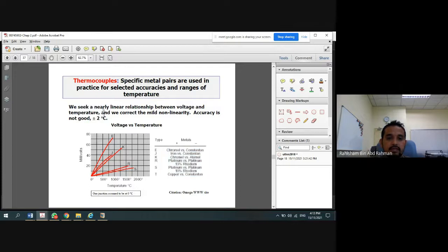Okay, and to a certain extent we can actually correct the non-linearity. For example, if we see K, what is K? It is chromel versus alumel. So we can see here the plot line is kind of linear. And this one, E, constantan, is linear for a temperature less than 50 degrees, but it becomes non-linear above 50 degrees. The same goes for any other. So based on this relationship, we can actually pick and select, or maybe correct, try to fix the non-linearity so that we obtain the desired value.